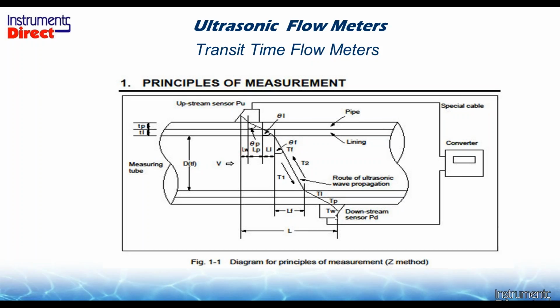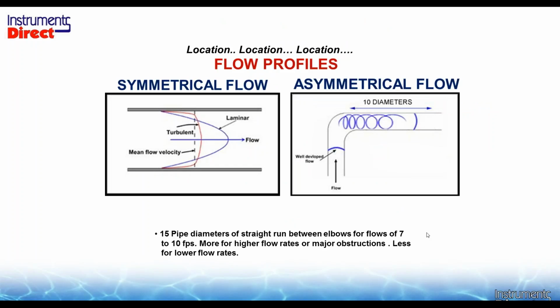Well, in the old days, you had to participate in that at some level, and now you're basically going to say to a drop-down menu, I have this transducer, I have this pipe material, I have this pipe size, and I have this pipe liquid, and I'm done, and move the sensors apart 2 inches. So it was very technical, and now not so much, and it has a lot more autopilot than it did before. Now, with every flow meter, there are certain guidelines and specifications where it works best. You may not have these all the time, but the quest is to optimize your performance to get your best accuracies, get your best numbers for whatever you're using it for.